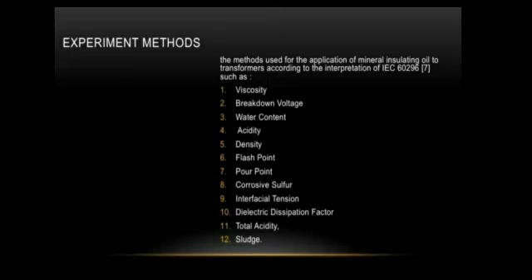Number 3, water content. Water content in the insulation will affect the breakdown voltage of the oil, the solid insulation, and the aging tendency of liquid and solid insulation. Number 4, acidity. The acid content or neutralization value of oil is the measure of acid components or contaminants in oil. Number 5, density. Density matters in order to prevent ice, resulting from freezing free water, from floating to the surface of the oil in cold climates. The density of the oil must be low enough, otherwise conductor jamming may cause disturbance conditions to develop.